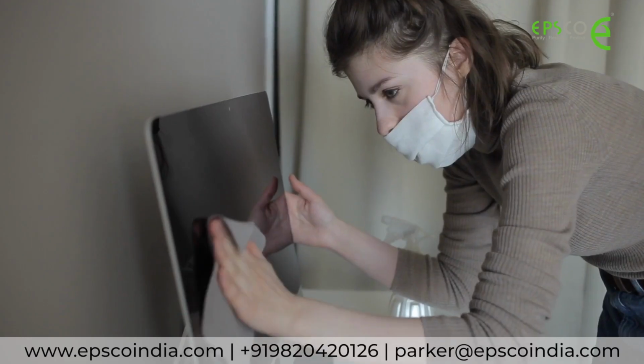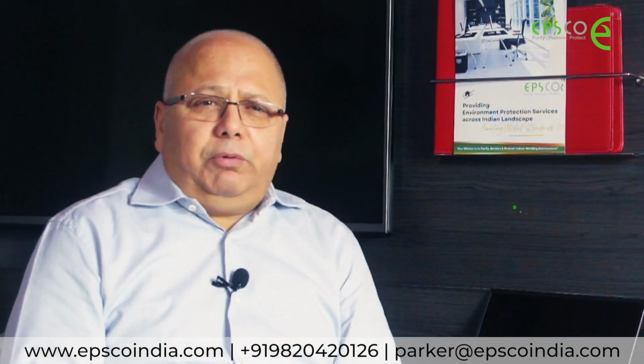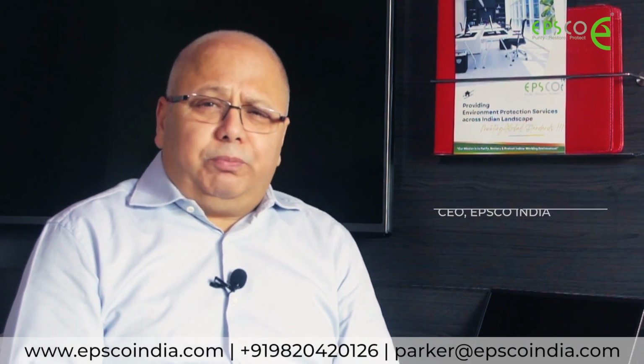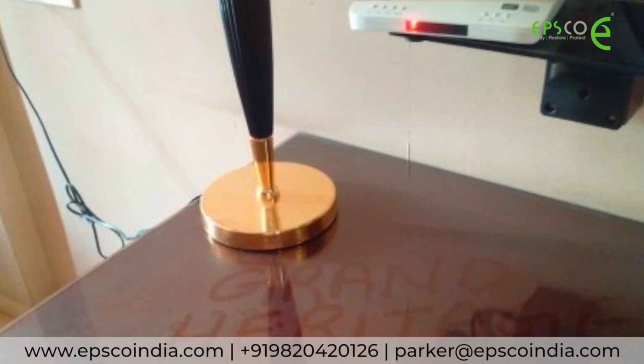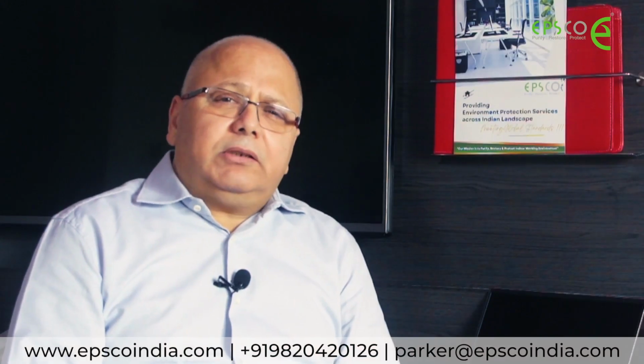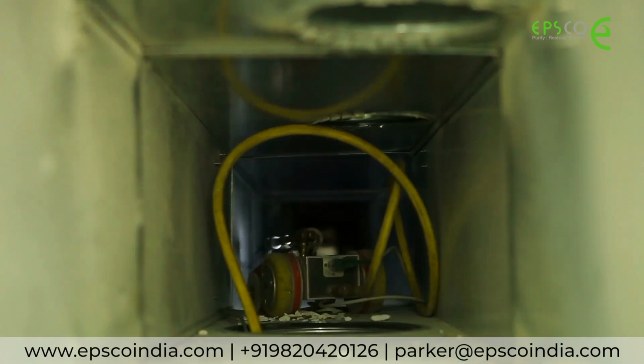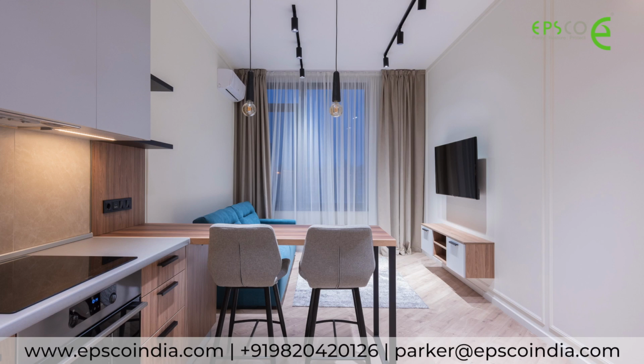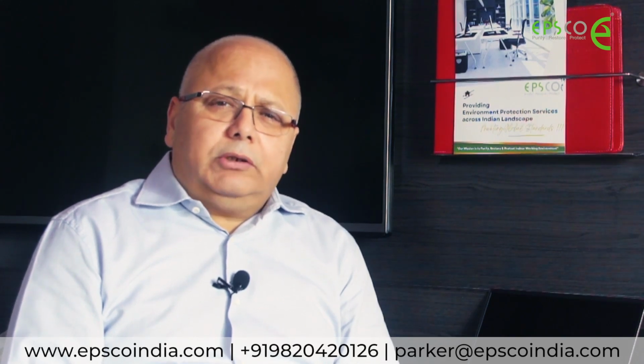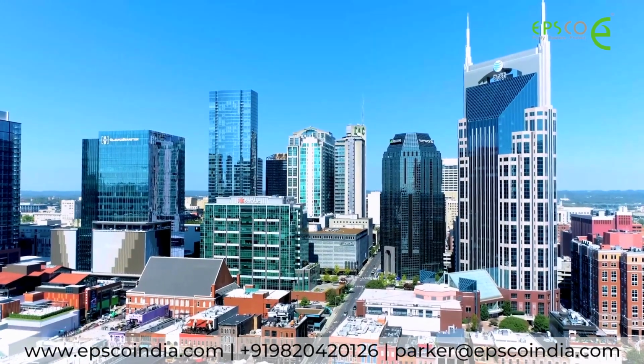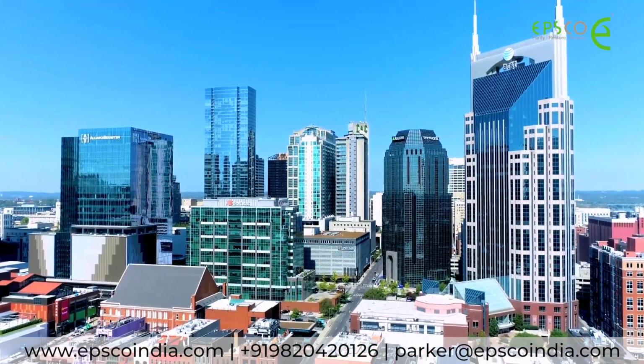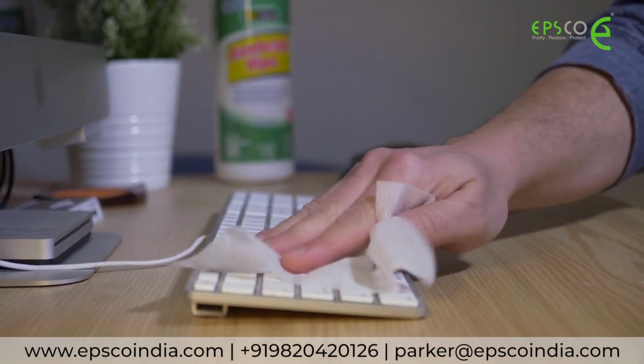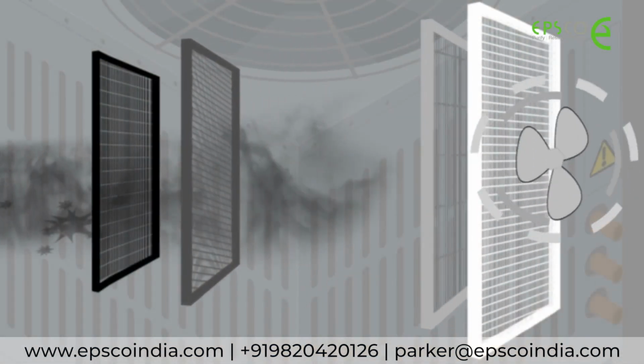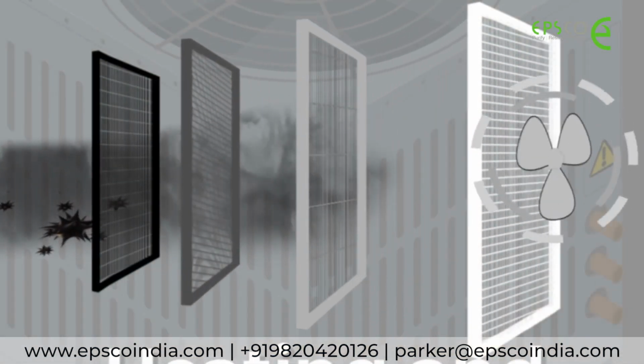Like everything you clean, we do housekeeping in our buildings. Even if you don't do it for 2 to 3 days, in Indian environment, it's so bad, you have dust on the tables. And you can actually write your name on it. Now just imagine you have the duct systems, the HVAC system, which are the lungs of your building, which carries cool air into the building, and again taking the warm air out into the system back again. So it's carrying air from the building right through and back in a circuit. All this dirt and debris which you're seeing on the table is also going into the duct system and passing through your filters and staying there over long periods of time.